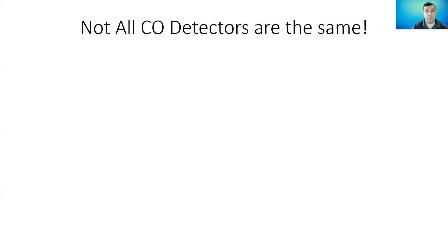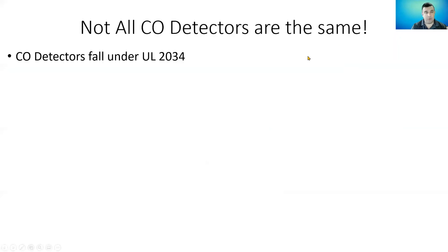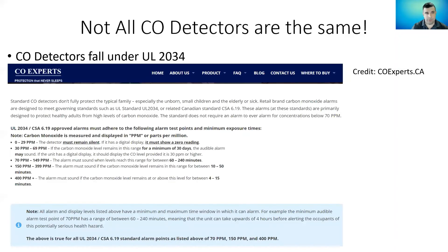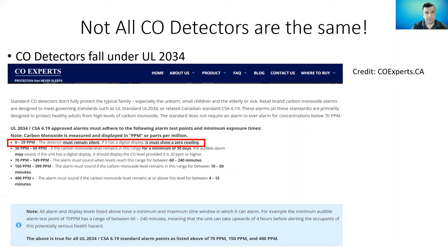Not all carbon monoxide detectors are the same. CO detectors fall under the UL listing 2034. From coexperts.ca — an organization dedicated to increasing education and knowledge about carbon monoxide hazards — here's some important information about UL 2034. Under this listing, from 0 to 29 parts per million, the detector must remain silent. It's not even allowed to tell you carbon monoxide is present at those low levels, and it must show a zero reading if it has a display. Just because you buy a carbon monoxide detector with a digital display does not make it a low-level carbon monoxide detector.